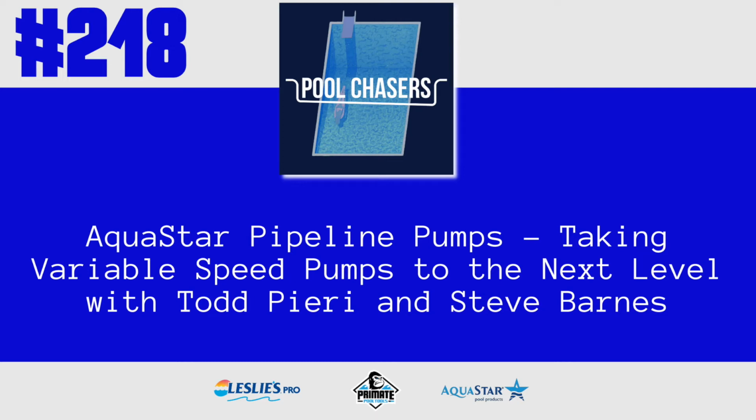So the focus, as I mentioned already, is ports through and through are 2.5 inch. So it really is the next generation of pump in that regard, compared to taking the very, very good quality pumps on the market now and putting variable speed motors on them. This was designed from the beginning for variable speed motors, and by that what I mean is the pump itself. If you've ever been on commercial jobs with big 25, 30 horsepower pumps, you will see those pumps are what's called a volute pump. And basically, the pipe comes off the side instead of dead center.